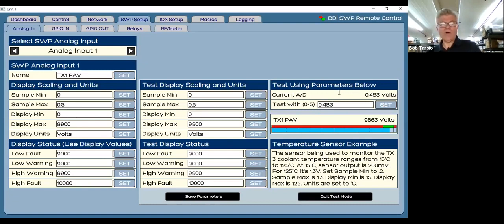I can go over here and set my parameters for what I want. I've already done this, so the minimum sample is 0 to 0.5 volts, you can see it's near the top, and that makes sense. The display minimum is 0 volts to 9900 volts, and it is voltage, so I put that in here. I put my fault and warnings in here, and that defines where the red, green, and yellow will be. If it gets into the warning, the yellow will appear to show you it's in the warning. Then you just save that, and you're done.